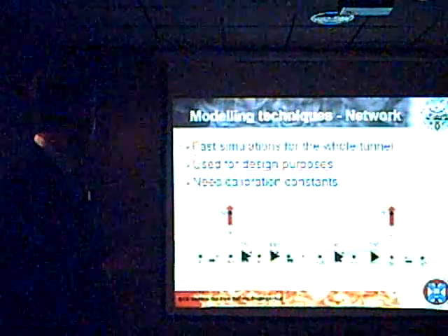So we can use different modeling techniques to deal with this kind of problem. The simpler one is to use a network model. The assumption under this kind of model is that all the fluid dynamic quantities like velocity, temperature, or density are constant across the section. Here we have an example: a small tunnel with 4 jet fans and 2 shafts. We can think of building a network of pipes representing the geometry. After calibrating all the constants, representing the fans like pumps and the shafts like branches within my network, I can completely forget the original structure and work with this kind of model.